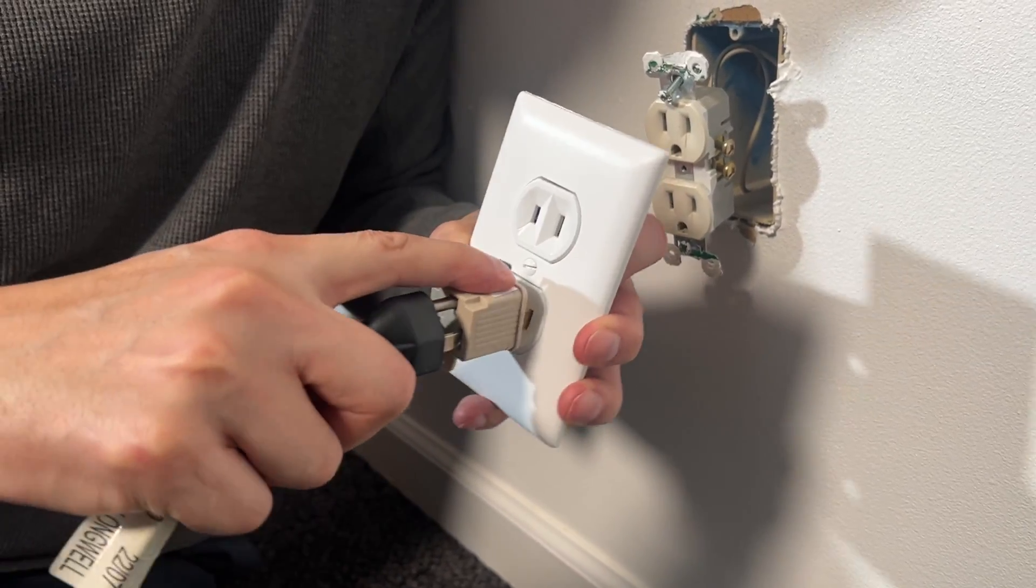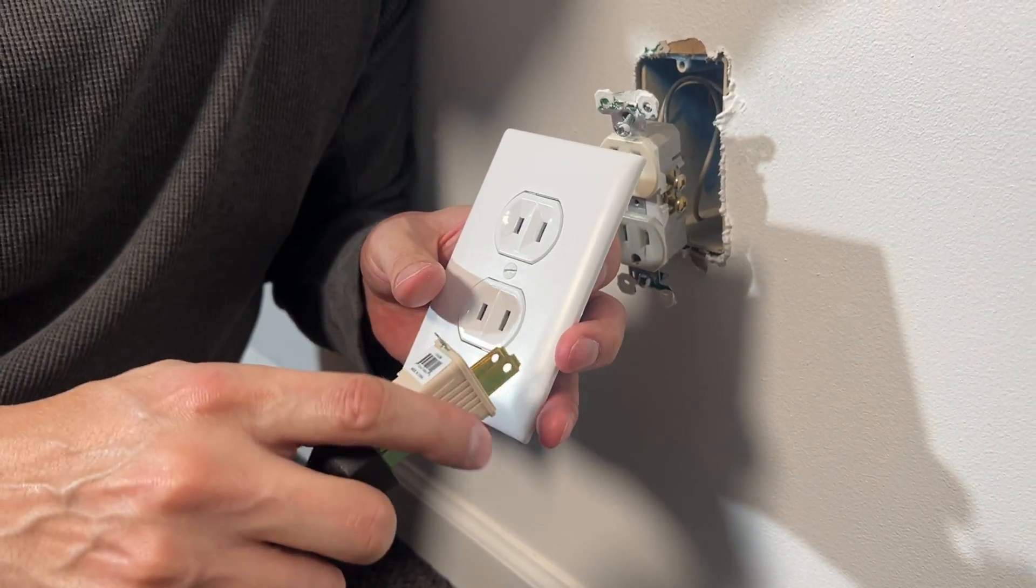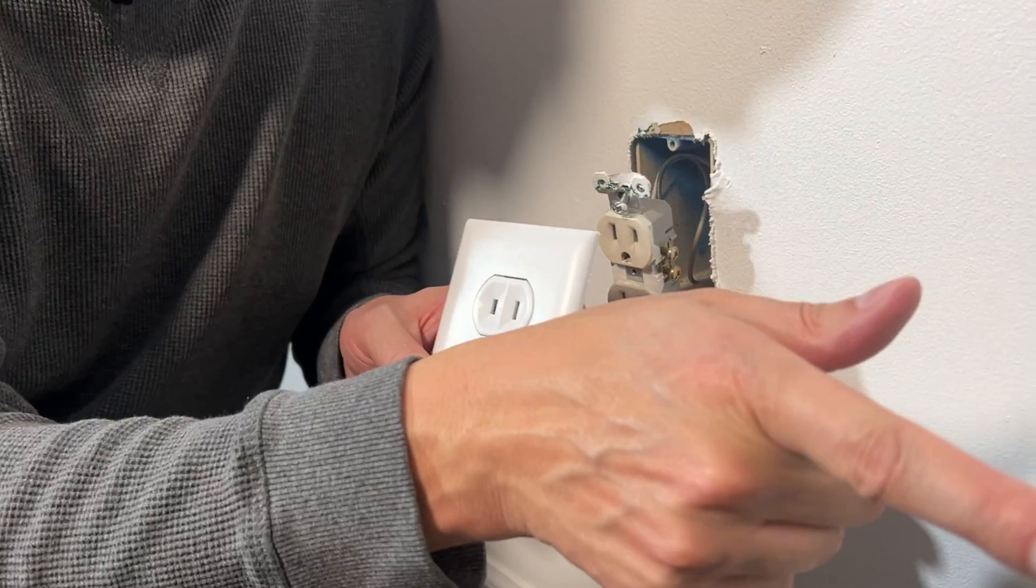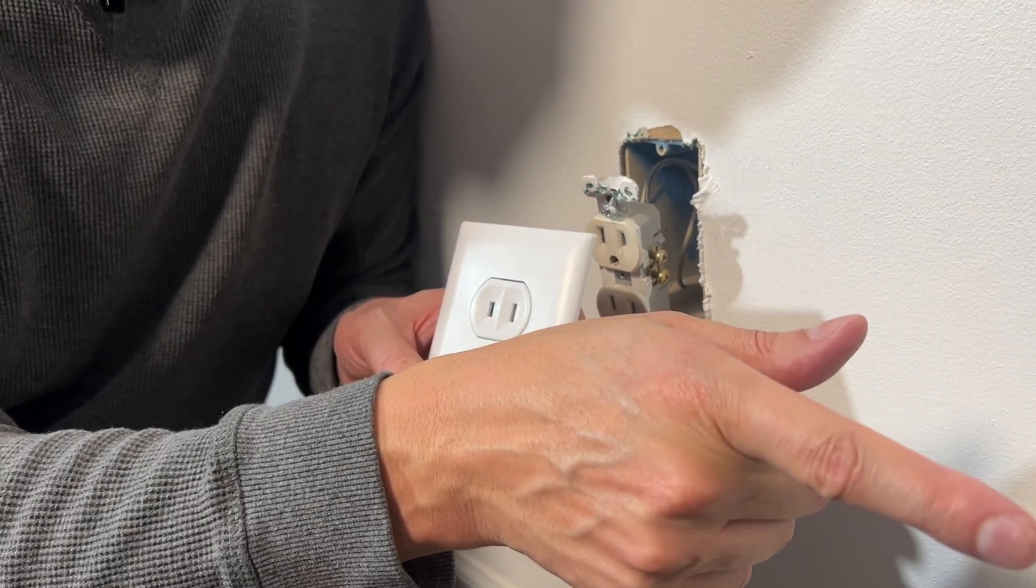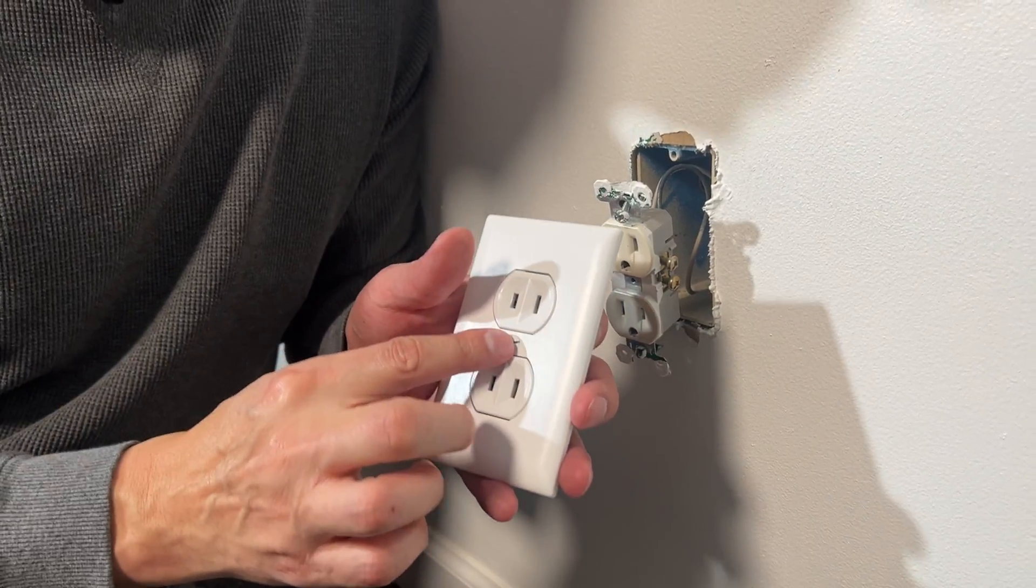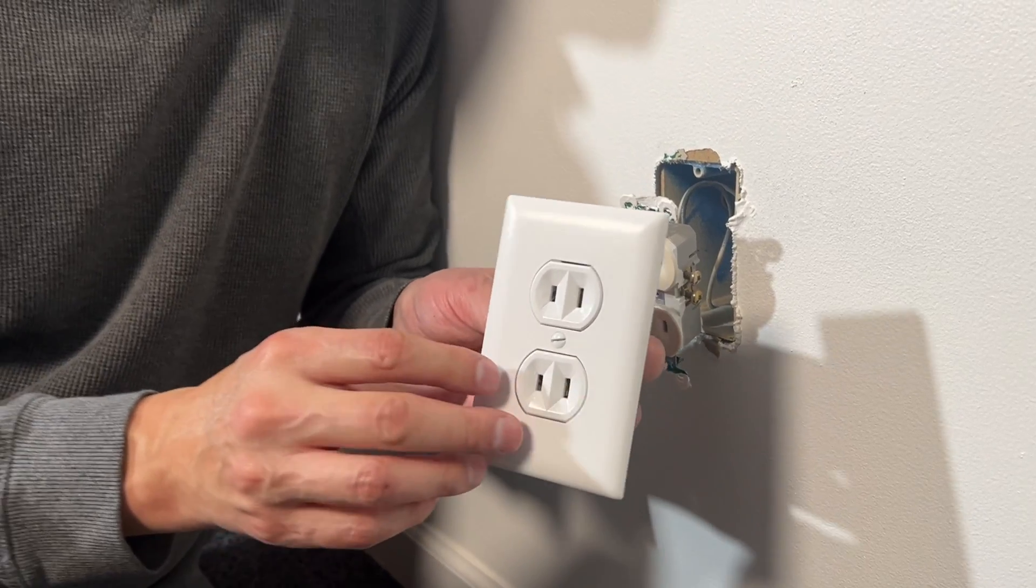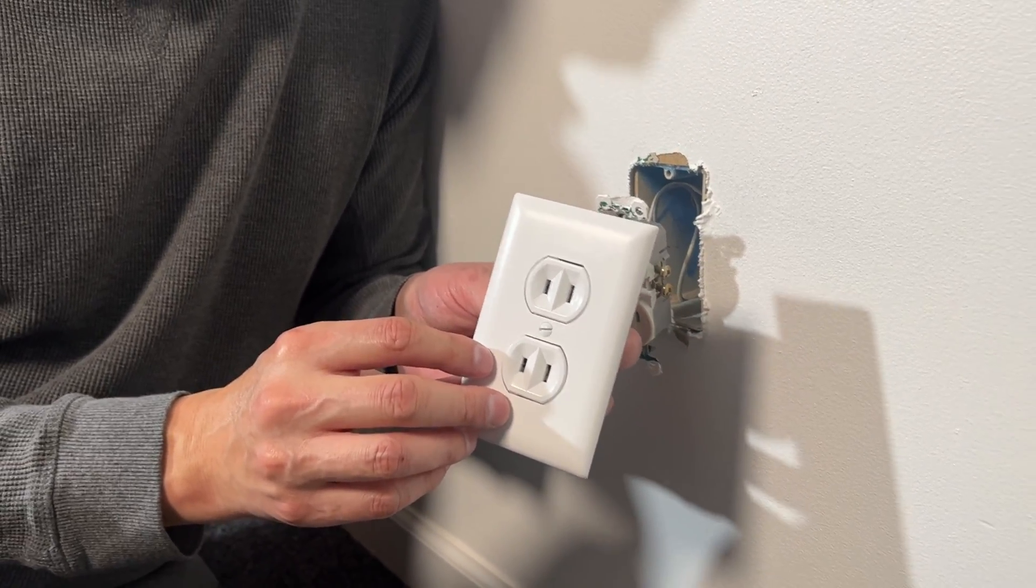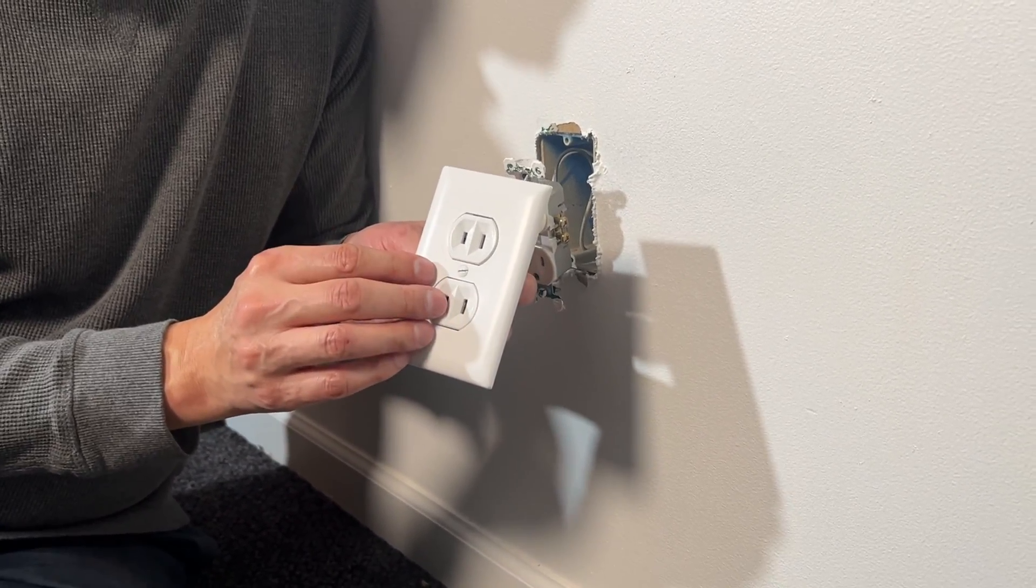Unless you have a metal electrical box and the metal box is connected all the way back to your circuit panel and ground, then you still don't have a safe connection. So even though this is option two, it's probably not the best option, but in some cases I have seen it.